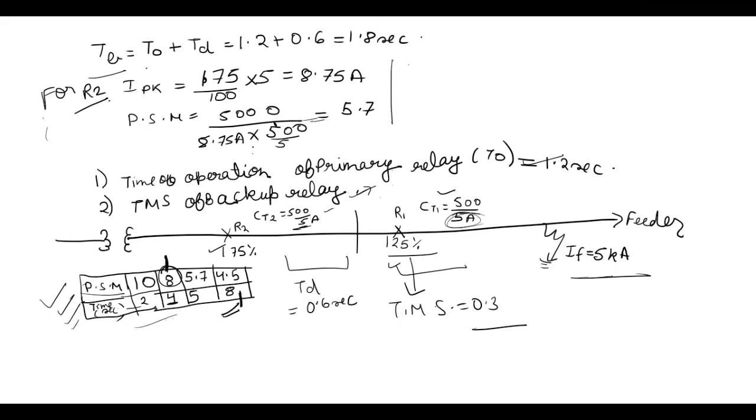So now time of operation T0 which is 1.8 second is equal to TMS into time calculated from IDMT draft corresponding to PSM 5.7. So now PSM 5.7 is this and now we are going to take time as 5. So TMS into 5. Therefore TMS is equal to 1.8 divided by 5 which is equal to 0.36. So TMS for backup relay is equal to 0.36.